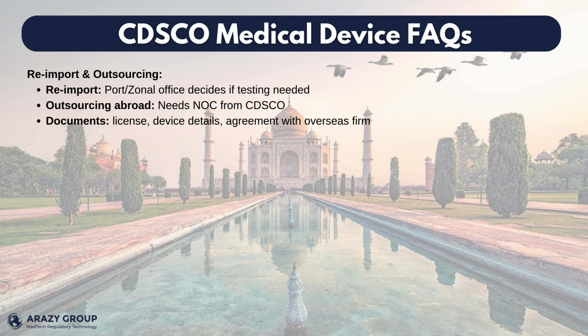In its July addendum, CDSCO provided clarifications on re-imports and overseas outsourcing. For re-imports, the requirement for laboratory testing prior to clearance is determined case by case by the Port Office in coordination with the Zonal CDSCO office. Regarding the outsourcing of activities abroad, such as coating, engraving, or batch testing, this is permitted subject to obtaining a No Objection Certificate, NOC, from CDSCO. Supporting documentation, including the valid license, agreement with the overseas partner, and device details, must accompany the request.